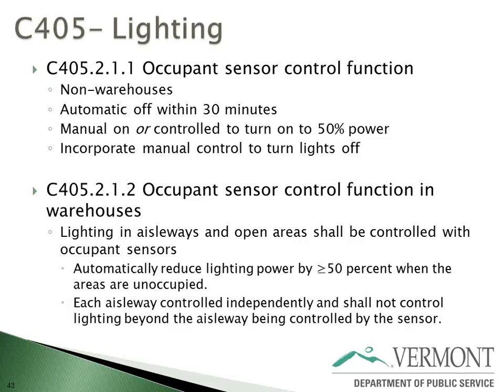I think the code has now actually gotten at that. So it gives the requirement for occupancy sensor controls, but it's not talking about warehouses, which you in fact deal with a lot. It needs to be automatic off within 30 minutes, but also needs to be manually on. It does allow it to come on automatically, but only to turn on half the lights, which I still think should just be manual on - an occupancy sensor should be manual on. It turns off if there's no activity, and you can always turn it off manually too. You shouldn't be forced to keep a light on.